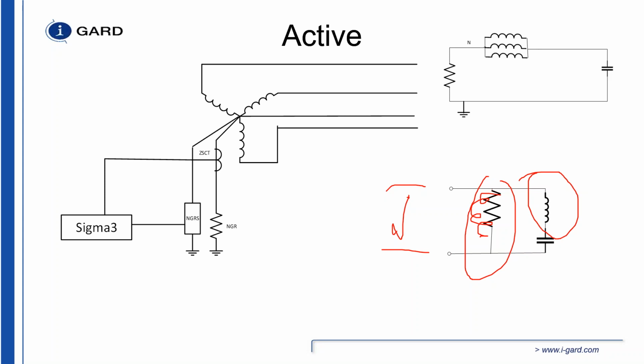I assume the resistor is going to be rated for 10 seconds because it's a 200 amp, so it's probably not a continuously rated resistor. The maximum pickup level of the Sigma relay is going to be 50%. If you have greater than a 50% fault, we're going to trip. And so the let-through current is going to be set for 200 amps, and you can trip that resistor from 5 to 50% of that.